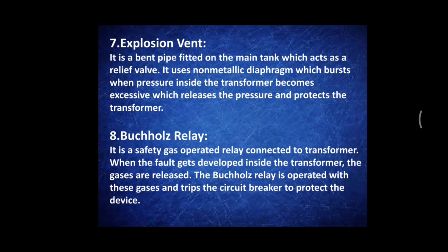The last element is the Buchholz relay. It is a safety gas-operated relay connected to the transformer. When faults develop inside the transformer, gases are released. The Buchholz relay is operated by these gases and trips the circuit breaker to protect the device.